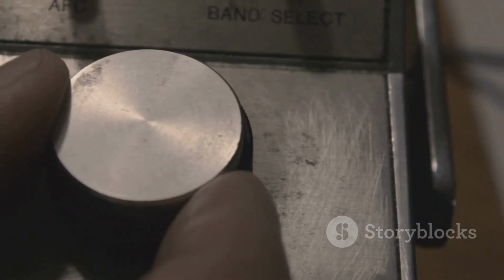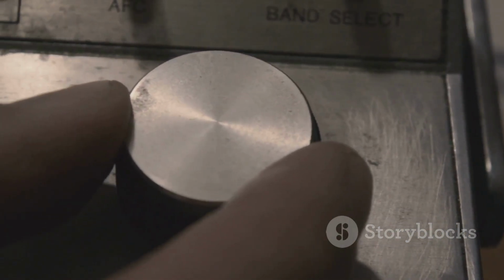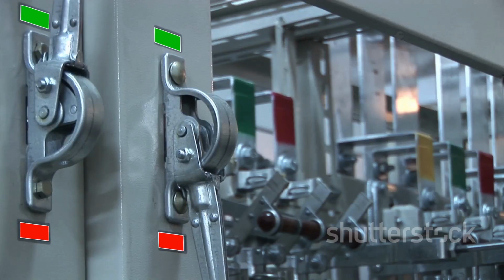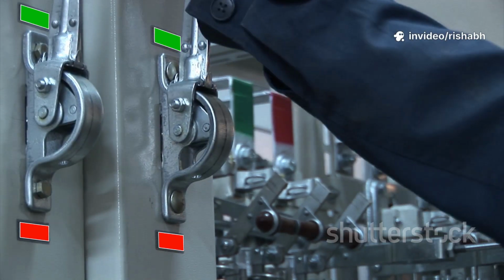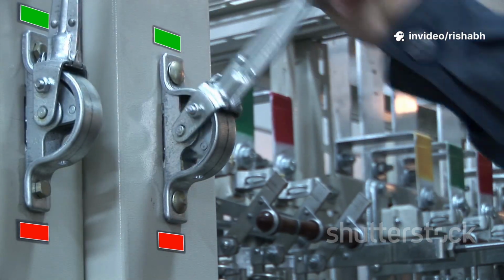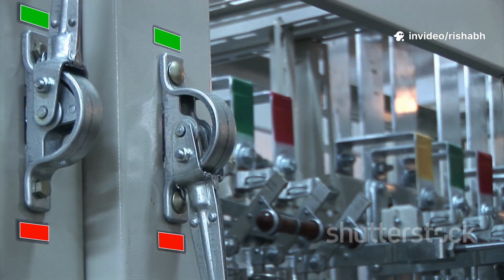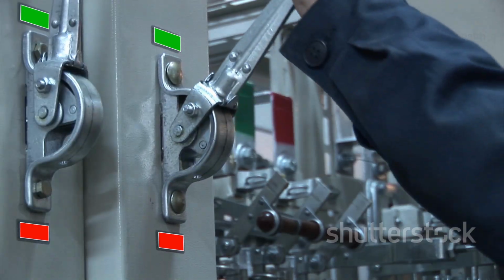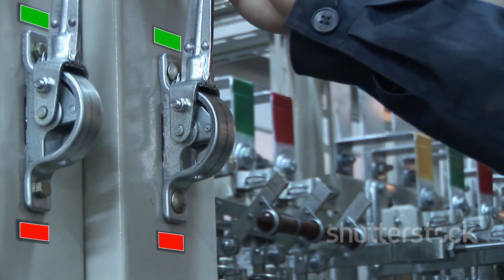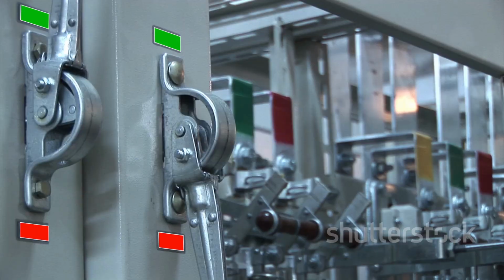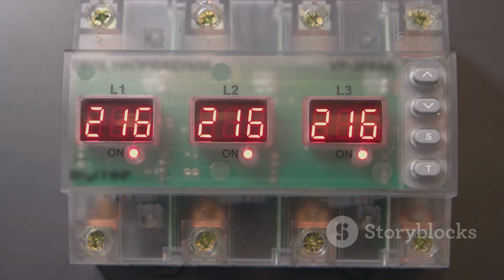When a tap change is initiated, the tap selector moves to the new position. Then, in a matter of milliseconds, the diverter switch rapidly transfers the load current from the old tap to the new one, using its transition resistors to ensure a smooth, arc-free handover. This ability to regulate voltage is absolutely critical for the stability of the power grid.